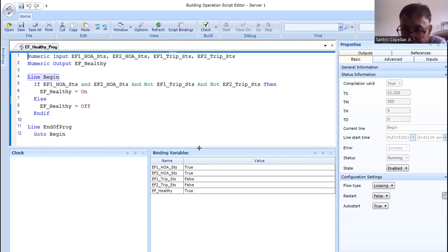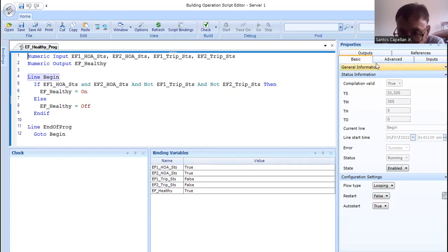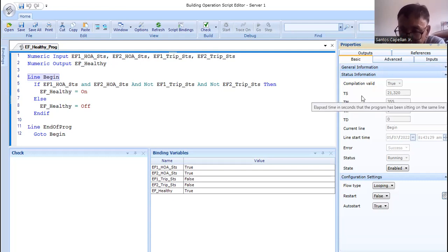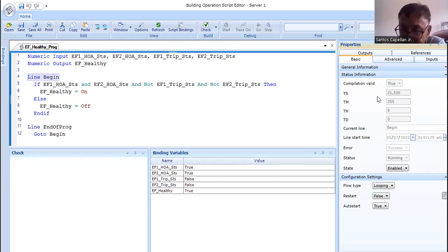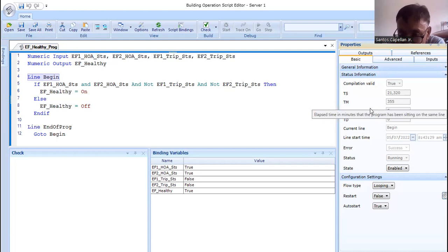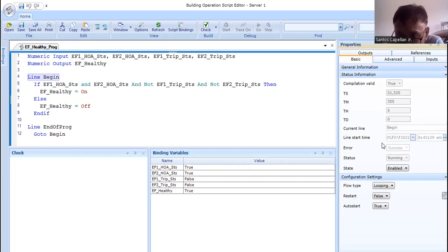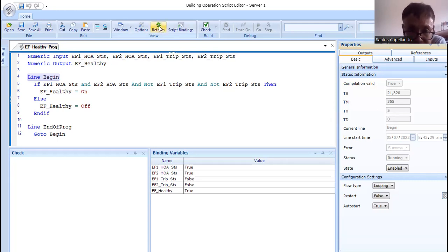This program is already enabled. Let me explain the different tabs. First, the basic tab — the most important field is 'compilation valid'. It should be true; if false, the program is not operational. Then 'TS' shows when it was started — you'll see minutes, hours, and day. Then 'current line' shows where the program is currently executing. This display is not real-time, so you have to refresh to see the current line. There should be no error — it should show success. If there is an error, the program will not do its work.